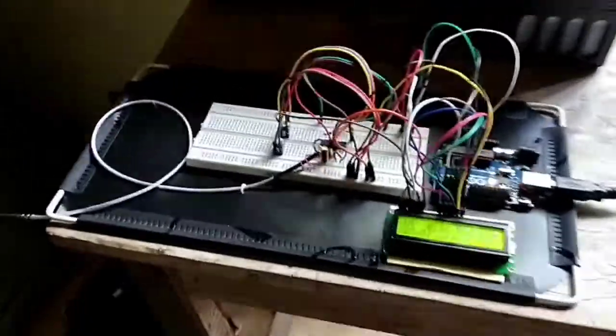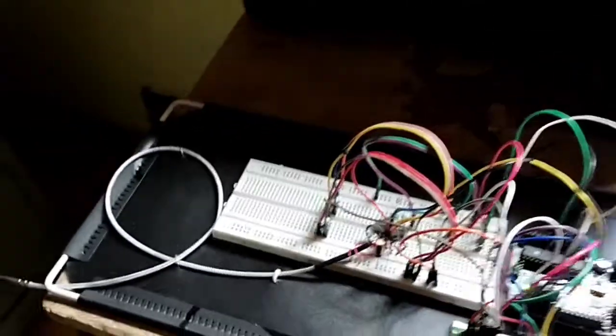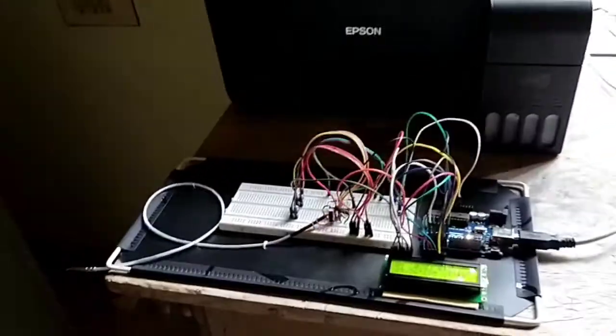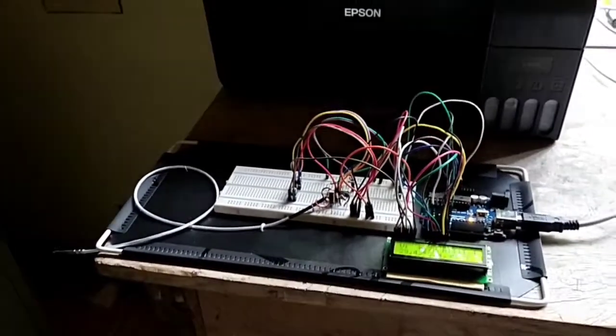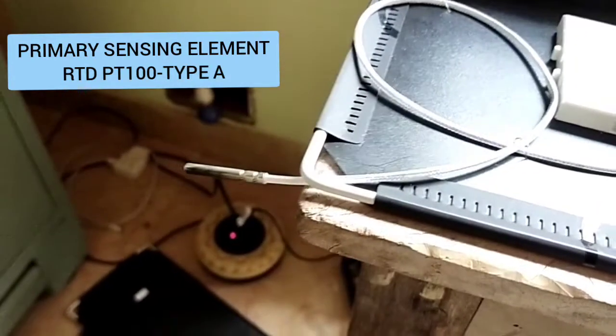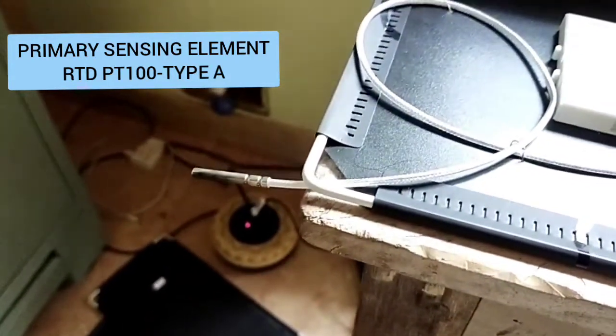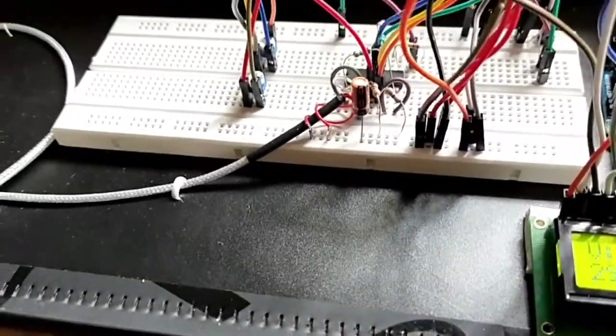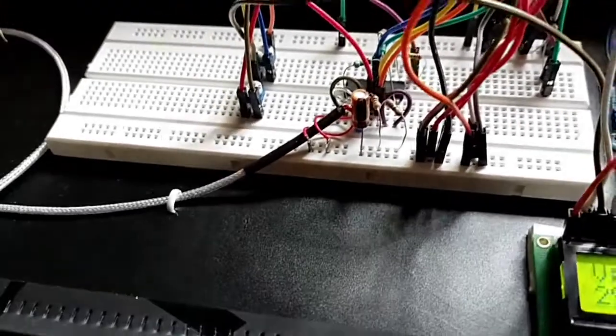This is the circuit which I have designed, comprising several components. This is the primary sensing element, a PT100 RTD type A with a 3-wire configuration, connected to the circuit board using the IEC 60751 standard.